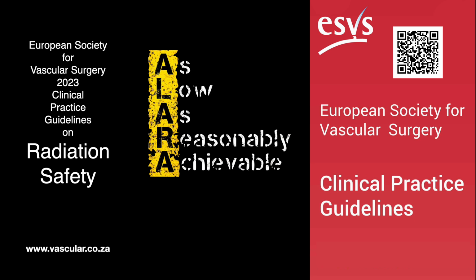And the guidelines stress that KAP/DAP and AK are preferred over just using fluoroscopy time, FT, for objectively measuring exposure. Why is that? Fluoroscopy time seems intuitive, how long your foot was on the pedal. It is intuitive, and it does reflect procedure complexity and maybe operator efficiency to some extent. But it's a really poor dose indicator overall. How so? Because it doesn't account for anything else: your C-arm settings, the tube current, the voltage, the field of view, any angulation, whether you're using low-dose fluoro or high-dose DSA. None of that is captured by fluoroscopy time alone. So you could have a short fluoro time but use really high settings or lots of DSA, and the dose could be huge. Exactly. Studies show it correlates poorly with KAP or AK. So while you track FT, don't rely on it as your main dose metric. KAP and AK are much more meaningful for dose audit. Okay. KAP and AK for objective dose.